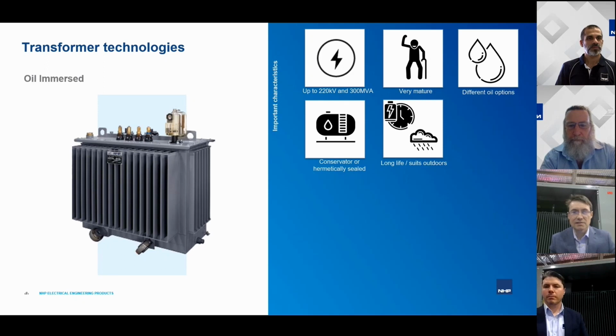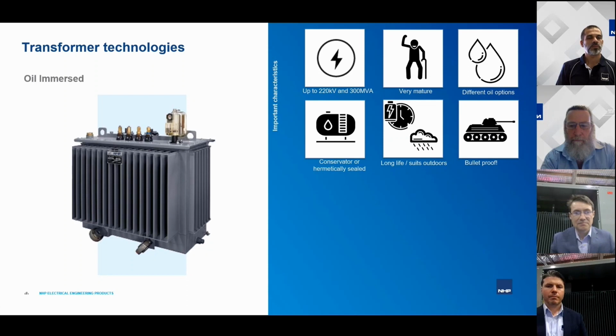Now, for oil transformer technology as such, it has a longer service life, going up to 50 years, provided it's correctly maintained. The key to transformer reliability and performance is the condition of its oil, and that condition can be easily tested. There are well-known methods to determine that and what the different impurities or components in the oil indicate about different types of faults. All this is very well known in the industry, to decide at which point the oil needs to be refined or even replaced with new oil, and then extend its service life. Of course, there are other components like gaskets, which deteriorate over time and could lead to leakages. Again, they can be replaced, and this way the life of oil transformers can be maintained up to 50 years. This is what we've seen pretty commonly in the industry, or sometimes they will even go over 50 years.